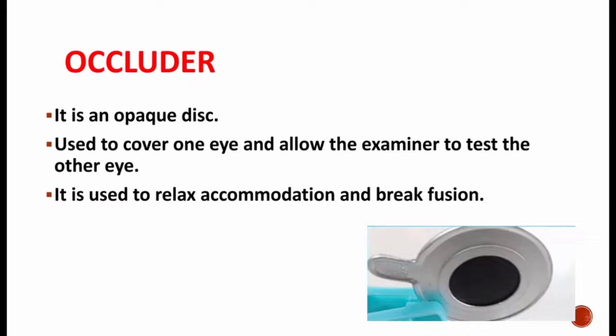For example, if we need to examine the right eye, the left eye should be occluded with the occluder. On placing the occluder in one eye, it breaks the fusion and it helps to relax the accommodation.